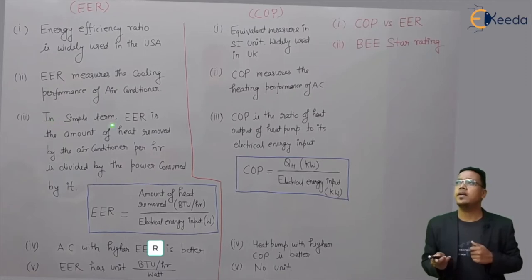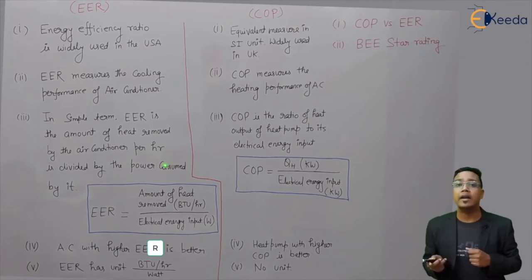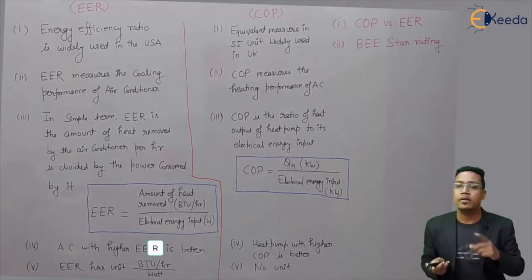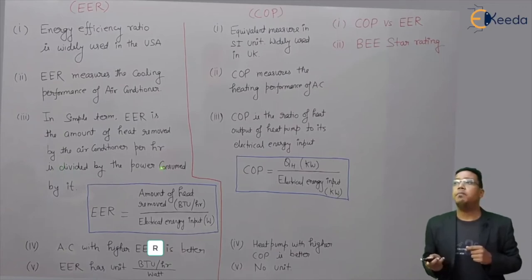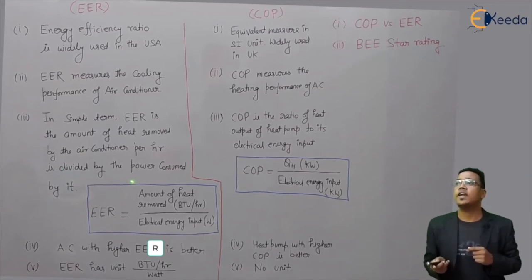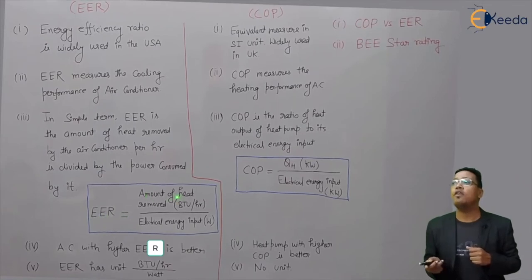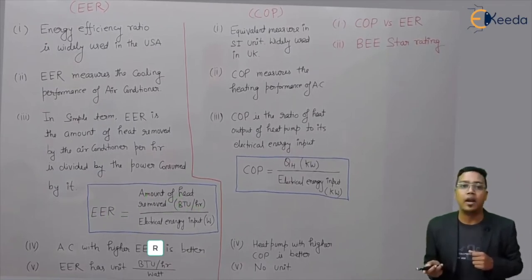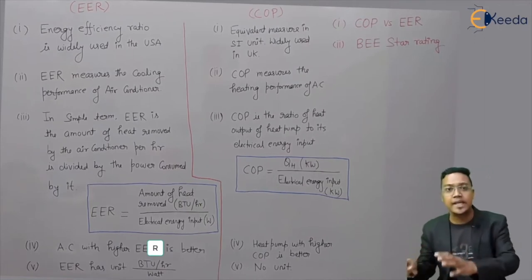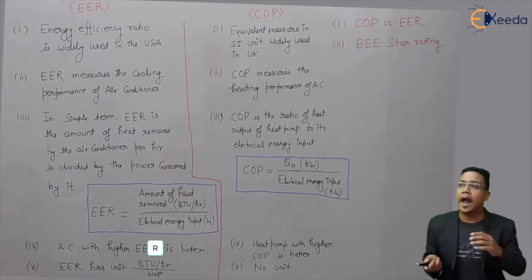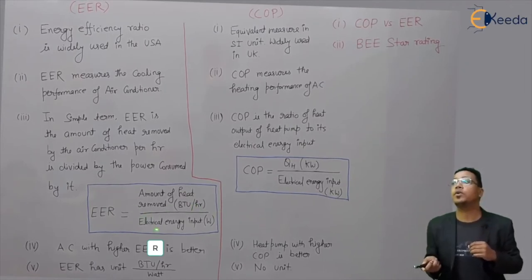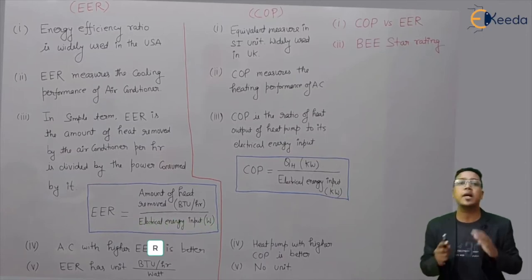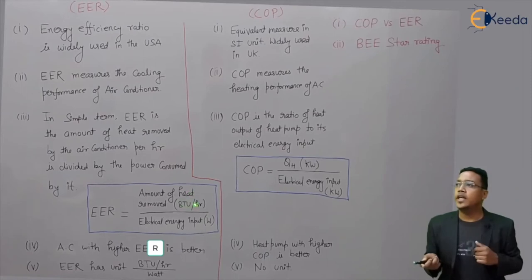In simple terms, EER is the amount of heat removed by the air conditioner per hour, divided by the power consumed. From this definition, we can write: EER equals the amount of heat removed by the air conditioner per hour in BTU per hour, divided by the electrical energy input in watts. Both these quantities give us the EER ratio. Higher EER means lower electrical energy input, so higher EER is better.